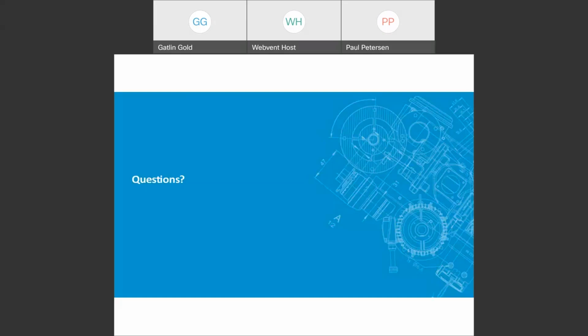Perfect. And then I see that Michael has replied, are bearings interchangeable? Generally, no. For any given product, whether it's a contact bearing or non-contact bearing, there's a specific bearing size for those contact bearings, the ball and roller, and you typically need to replace them in kind. And then same thing on the airfoil and magnetic bearing turbos. Once those machines are in place, you typically need to replace with the exact same bearing each time. There's not usually retrofits available, at least that we're aware of.